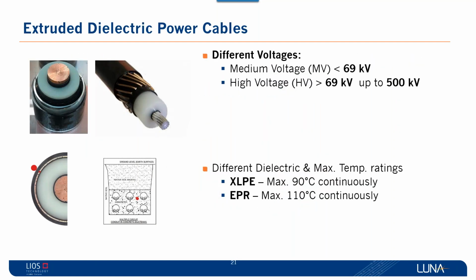Just a brief background, because I'm pretty sure a lot of people are familiar with this. The idea is that you have different power cables. You have dielectric power cable, you have oil-filled power cable as well. What we care more about is the dielectric power cable. We have medium voltage, high voltage, up to 500 kV. And the limitation of these cables is always whether or not they can sustain the temperature during operation. Every time you have ampacity, or electricity, flowing through the conductor, the cable overheats, and the limitation is the insulation or the dielectric.